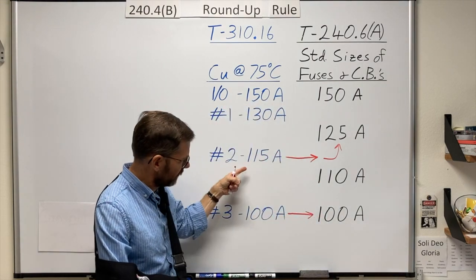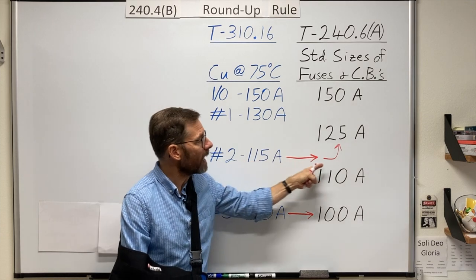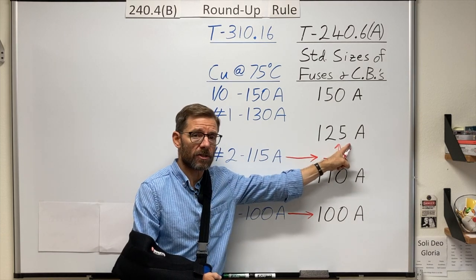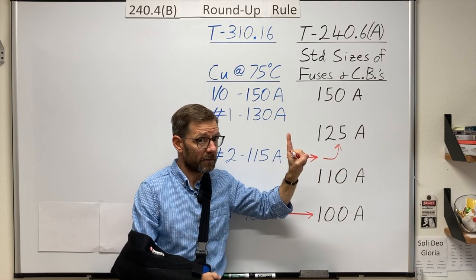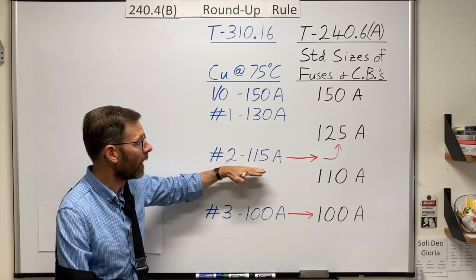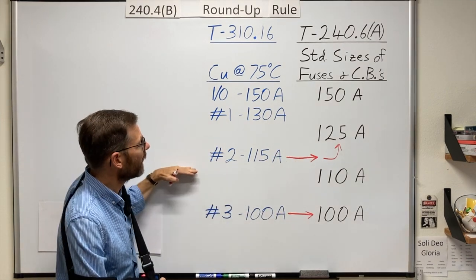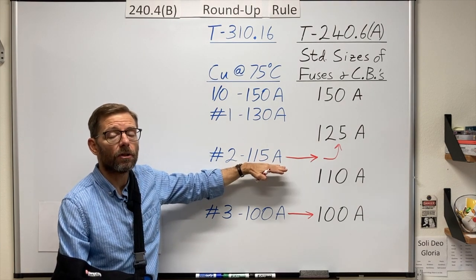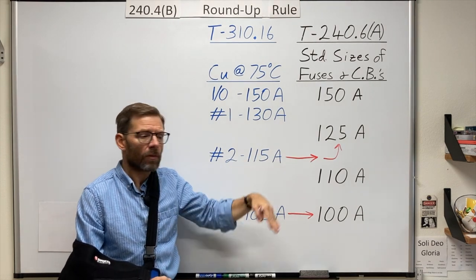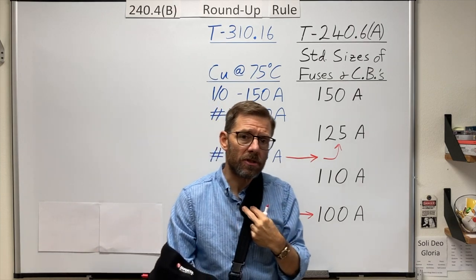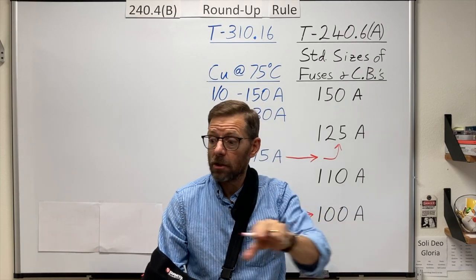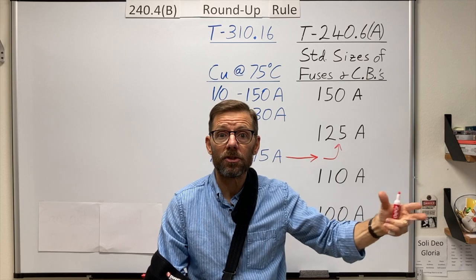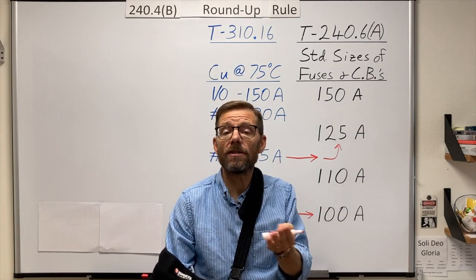The conductor can be protected by the next bigger size, but we are not allowed to, we cannot run more amps on this conductor than its rating. So that's our job as electricians. When we make installations, to know what's connected to our conductors, to make sure everything's sized adequately.